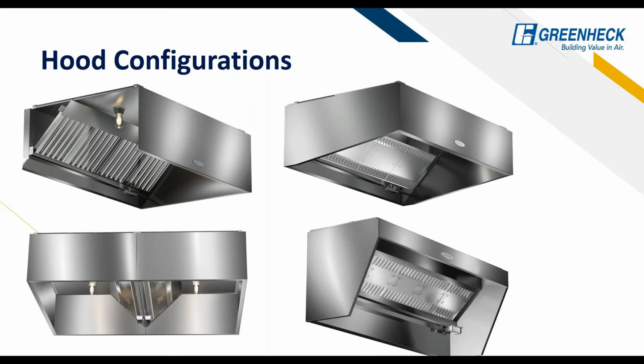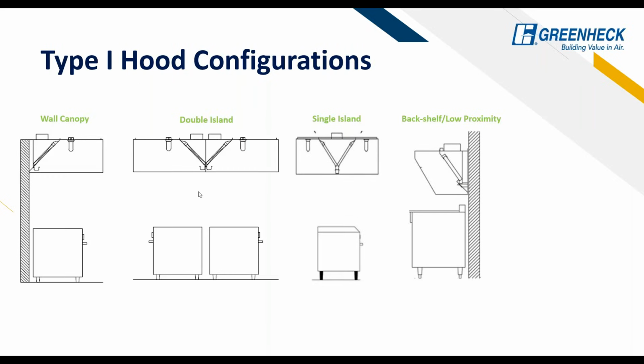And we can also do tapered fronts as well. So on this wall canopy hood on the left here, sometimes you can't get 80 inches above finished floor on these. So we can actually have a 24-inch back, and it will come out, and then it'll actually taper up to the front and only have a 12-inch overhang on the front. So we can actually have the bottom of the hood up here and allow for a little bit tighter space. So when you have low ceiling applications, you might see us recommend a tapered front hood. They do require a little bit more CFM, as you are losing a little bit of performance from the hood as well.